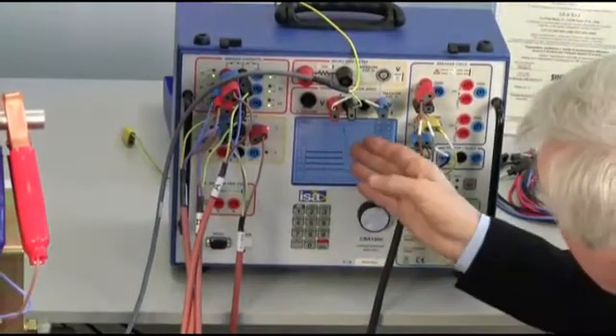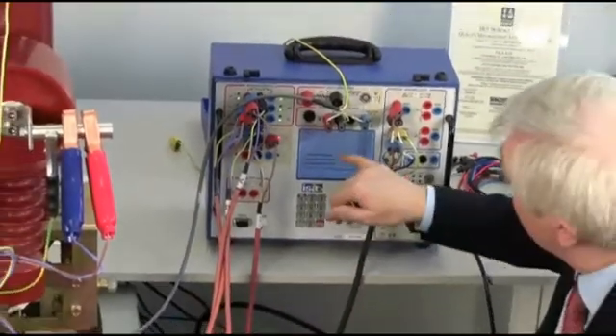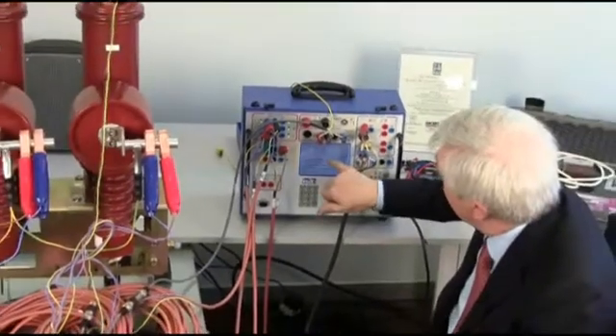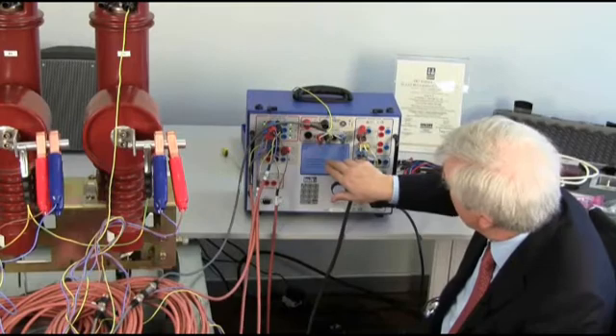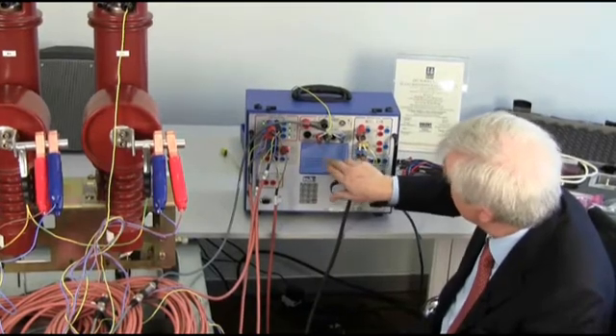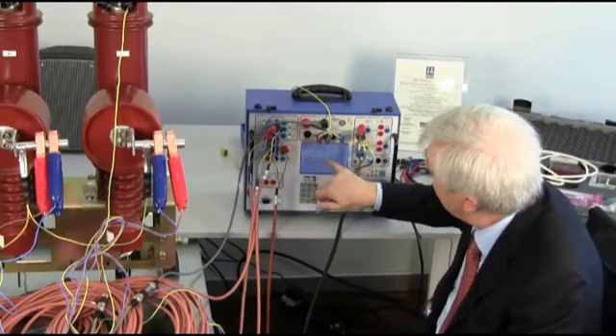So, this is the actual movement of your pole. And why is it important? Because if you have an end stroke, a mechanical end stroke against which your mechanism is going to beat during the opening, then you can see it.